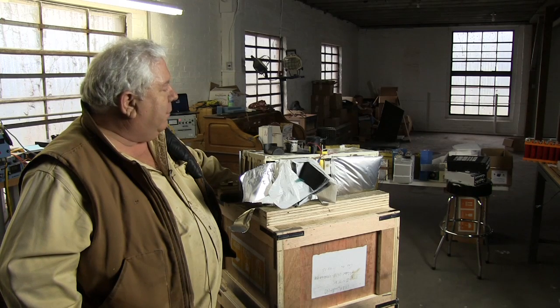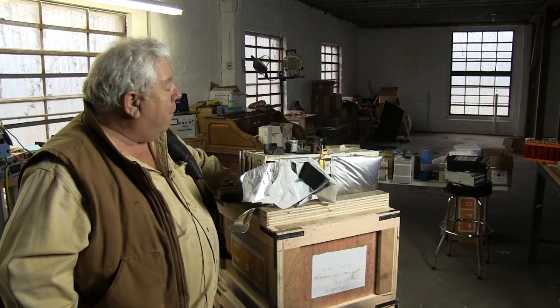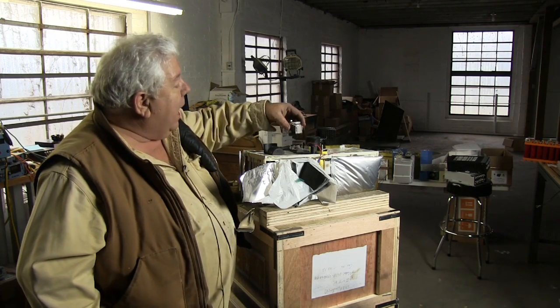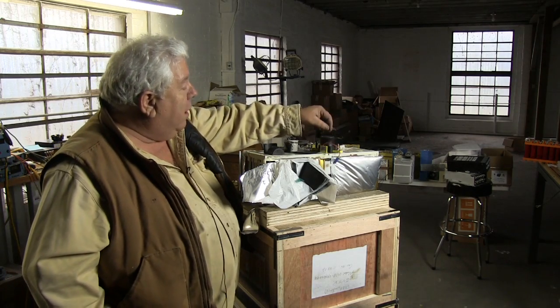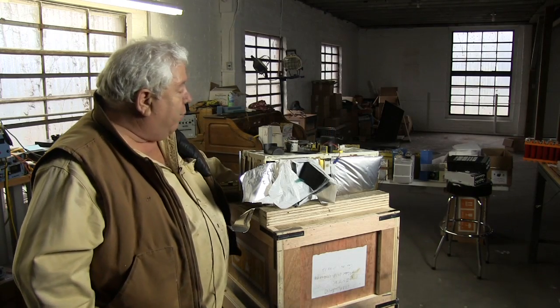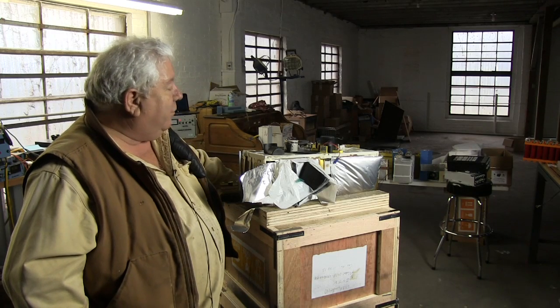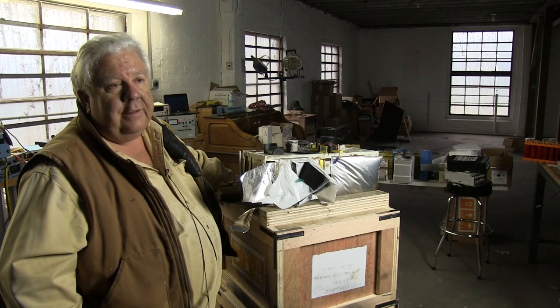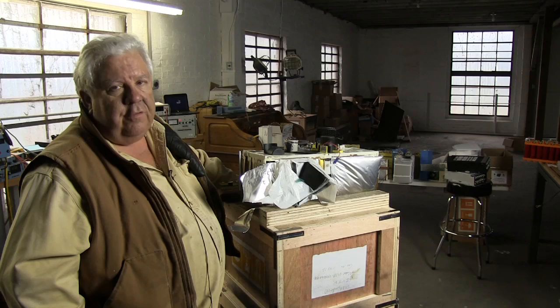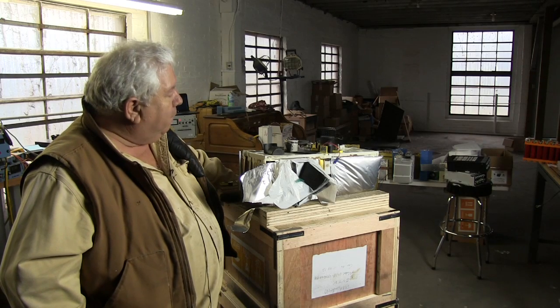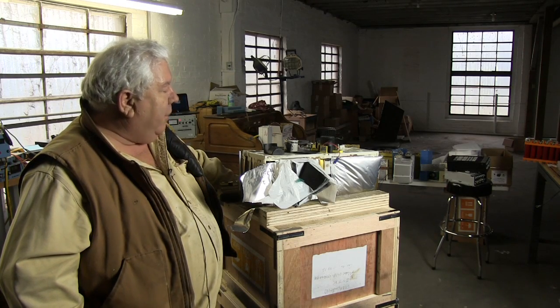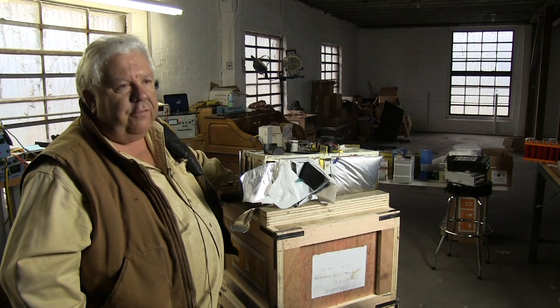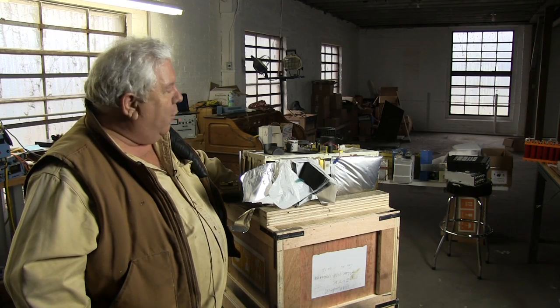You just have to check the basics. What had happened was both of these contactors had welded themselves shut. It's probable one of them had failed at some point and I hadn't noticed, because the other one was still working — which is the problem with a backup system like this. When one element fails, if the other is working you don't notice the failure. Then the other one fails too, and it looks like both failed at the same time. Probably didn't happen that way.